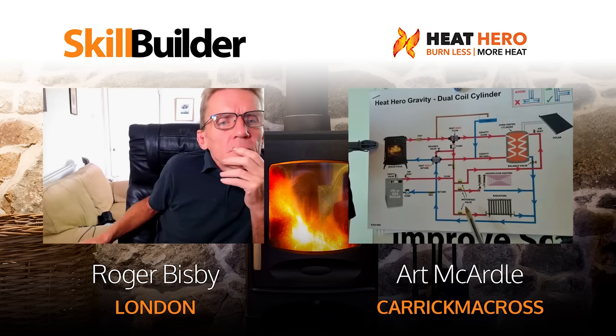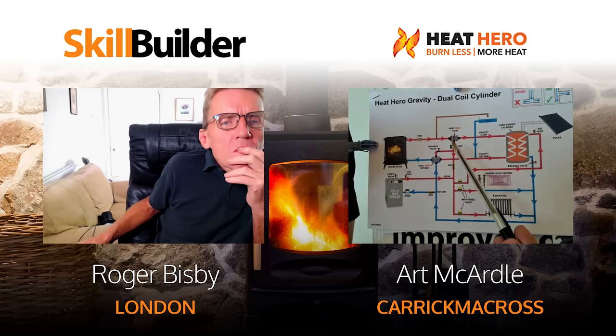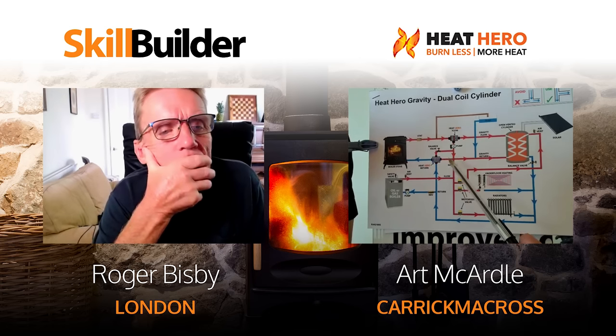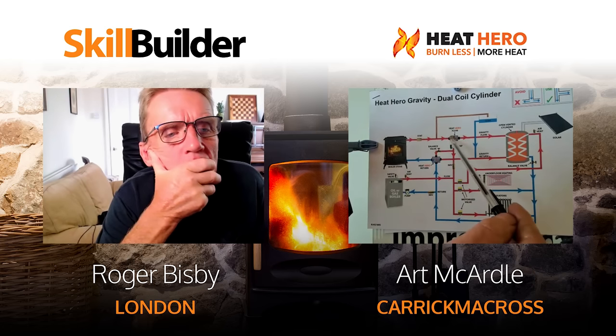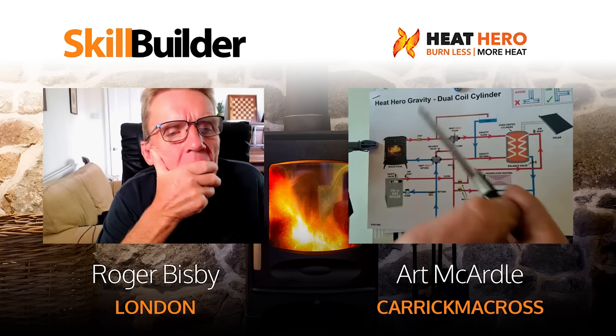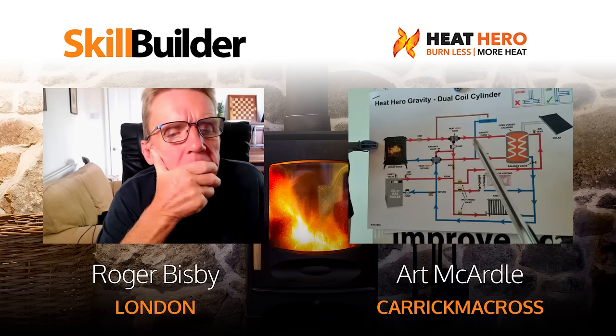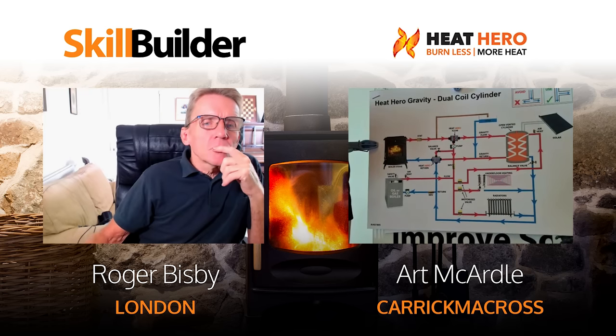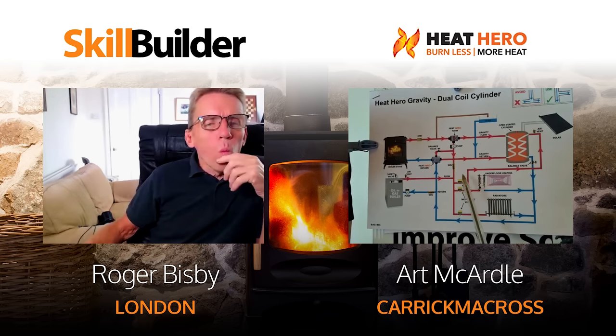Plumbers all over the island are fitting these now. They recommend to the customer fitting the 8-metre pump and the two Heat Heroes. On a standard system it takes about an hour and a half to fit - you're only moving the pump from one pipe to the other and replacing two T's with two manifolds. You'd still need to drain and fill the system, so you could be talking about half a day in total. There was never a proper system for solid fuel until now - this is a system an apprentice can install and be guaranteed to get full efficiency from the stove.